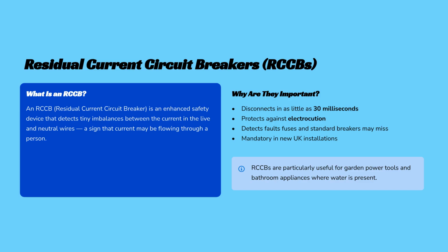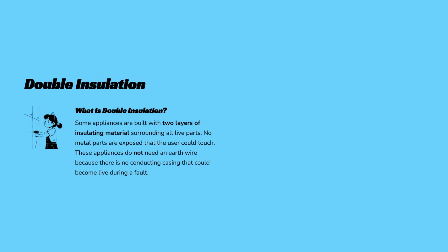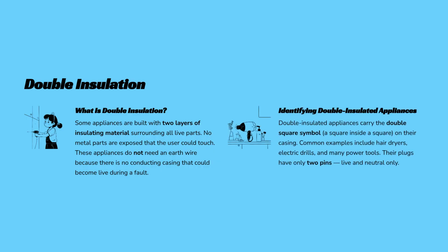An RCCB, or residual current circuit breaker, is an enhanced safety device. It detects tiny imbalances between the live and neutral wires, which could indicate electricity is passing through a person. It acts in milliseconds to prevent electrocution. Double insulation is a safety feature, where live parts are protected by 2 layers of insulating material. These devices have no exposed metal, so they don't need an earth wire. Look for the double square symbol on appliances like hair dryers.